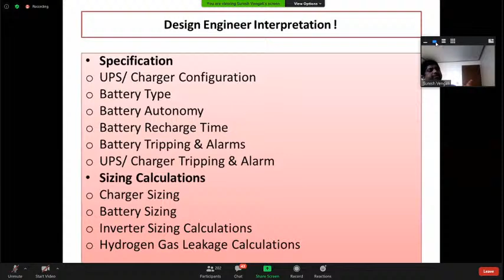Then you need to initially think about temporary HVAC. If you don't have temporary HVAC, what will happen? In the initial construction or commissioning phases, some guys may be lazy or may not follow the rules strictly, and when you start the charging application, your battery will generate hydrogen gases. So temporary HVAC is a very crucial item when you are commissioning a battery, and you must always keep in mind that we need to maintain the battery room at 20 to 25 degrees.